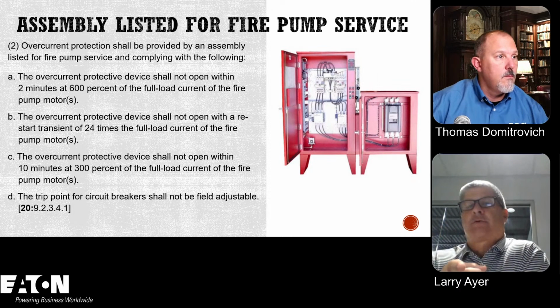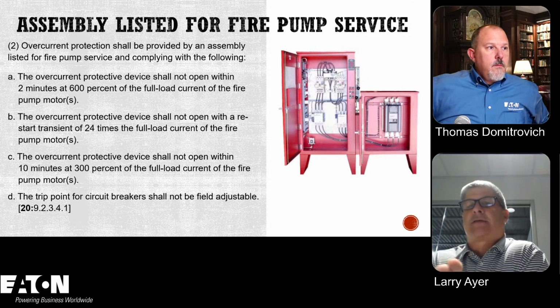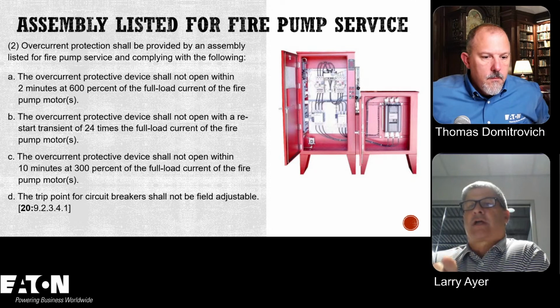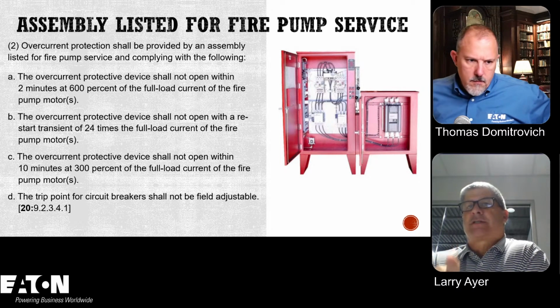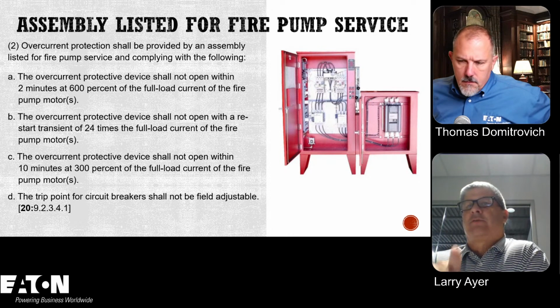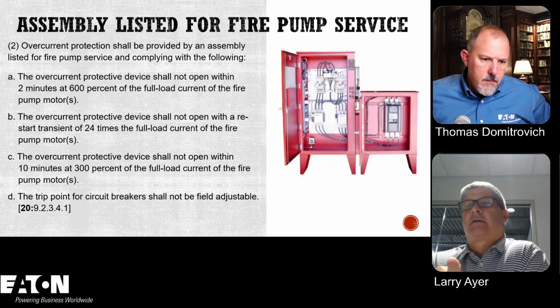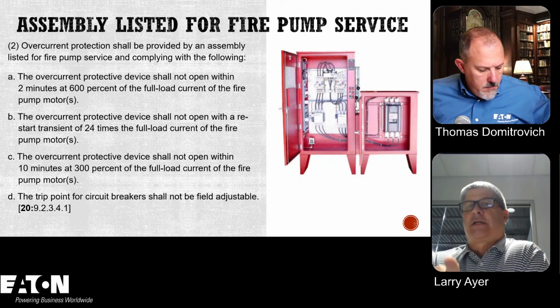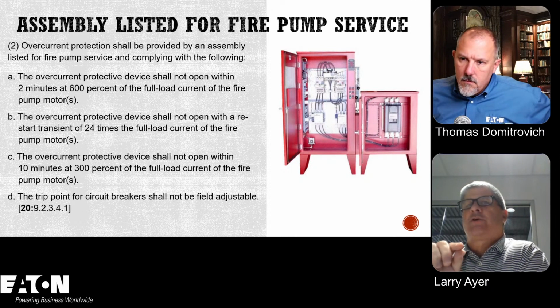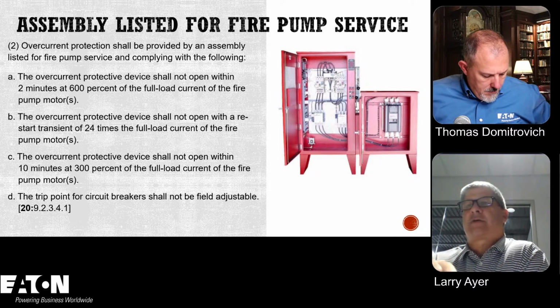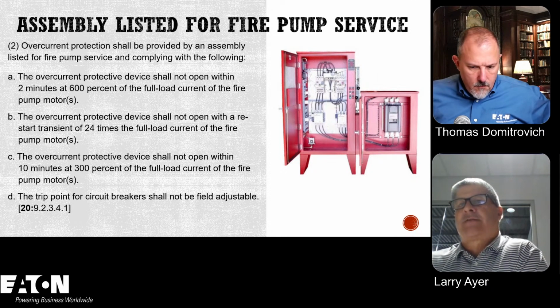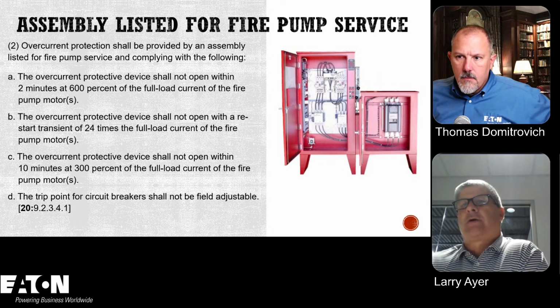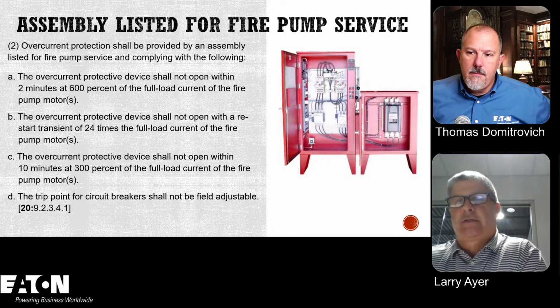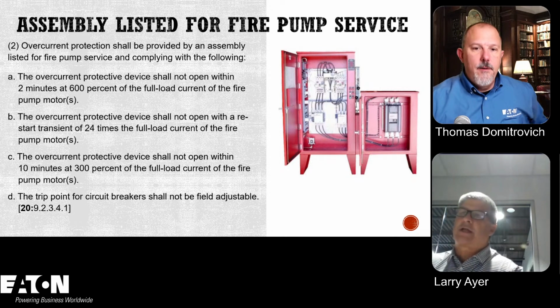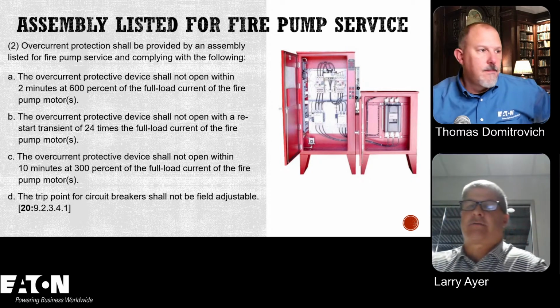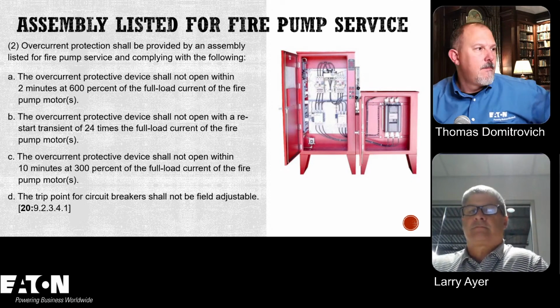Correct. And going back to Bruce's question, I don't know if he meant to say this or not, but a transformer does not have to be sized for full load of 600% of the locked rotor. You have to size it at 125% of the fire pump, but you have to worry about the voltage drop, and that's where the 600% comes in. Okay. So that's what he might have meant. I just want to make sure I clarify that. All right. Good point.